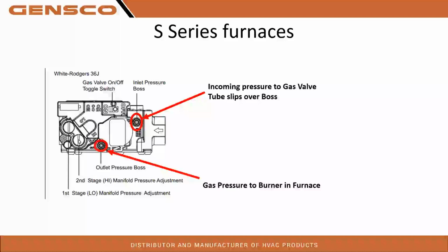The install guide does say when you pull these, either they're black anodized or brass low or high caps, you want to put your thumb over them, make the adjustment, put your thumb over them to basically seal them back up, or put the cap back on it. Okay, that is a recommendation from the manufacturer itself. So on the S series furnaces, we're going to go with either a single or two-stage J style valve.